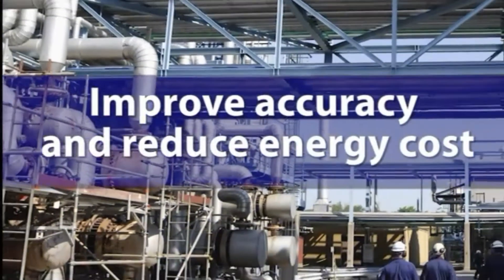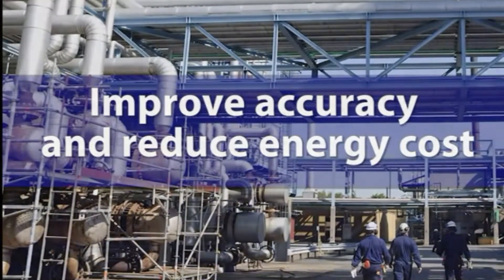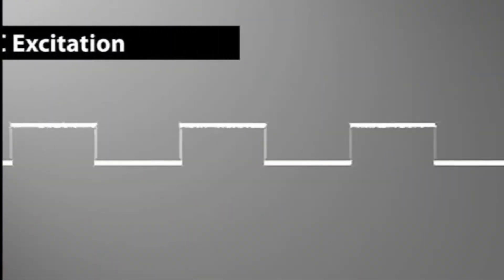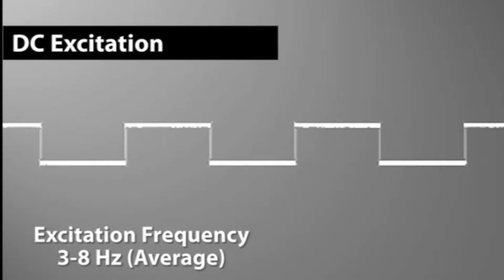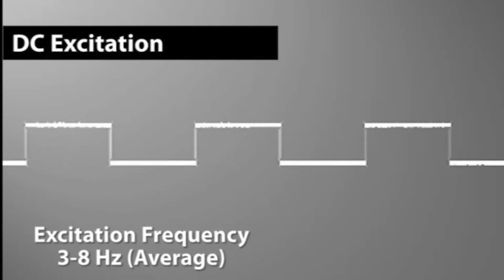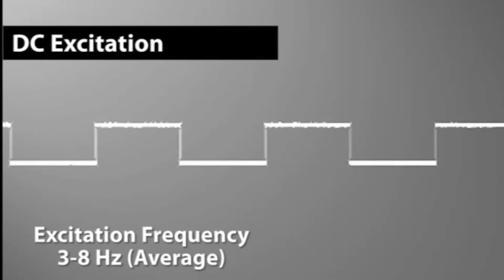In an effort to improve accuracy and reduce energy cost, pulsed DC-type excitation was introduced several years later. The average excitation frequency is between 3 to 8 hertz, but can go as high as 30 hertz.